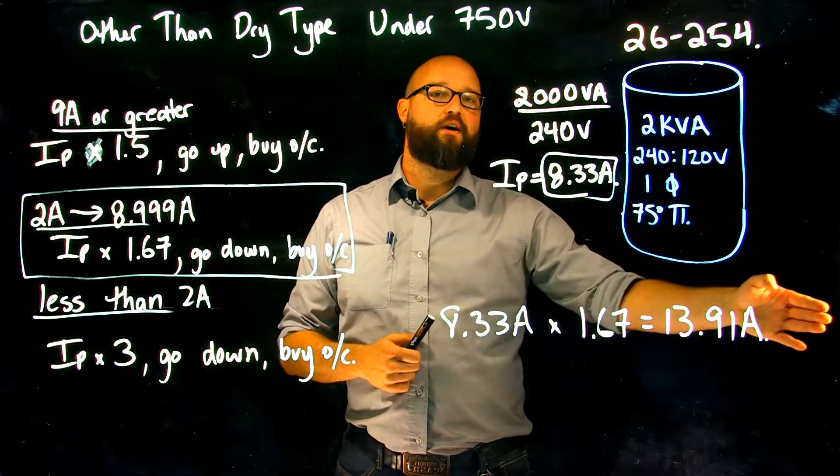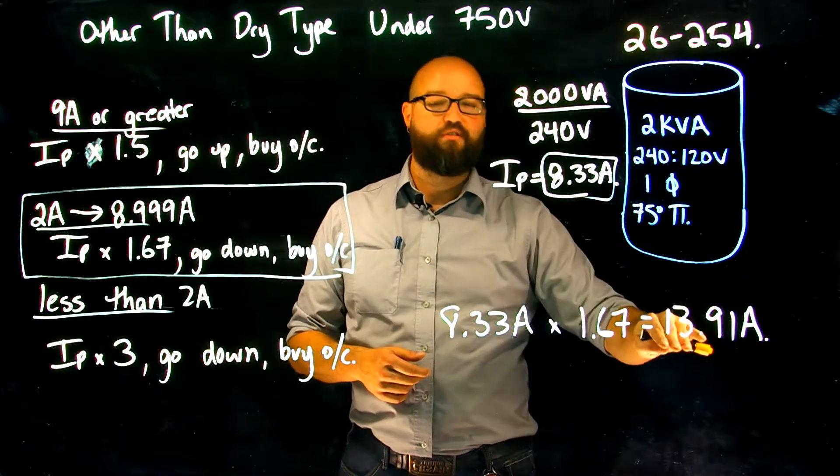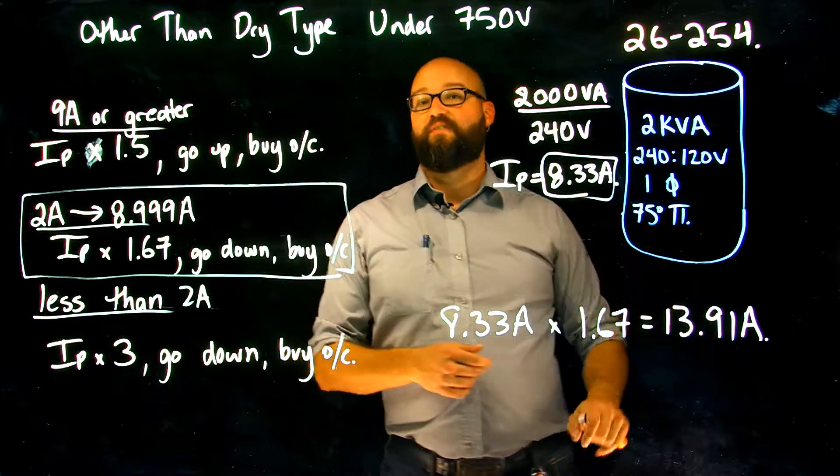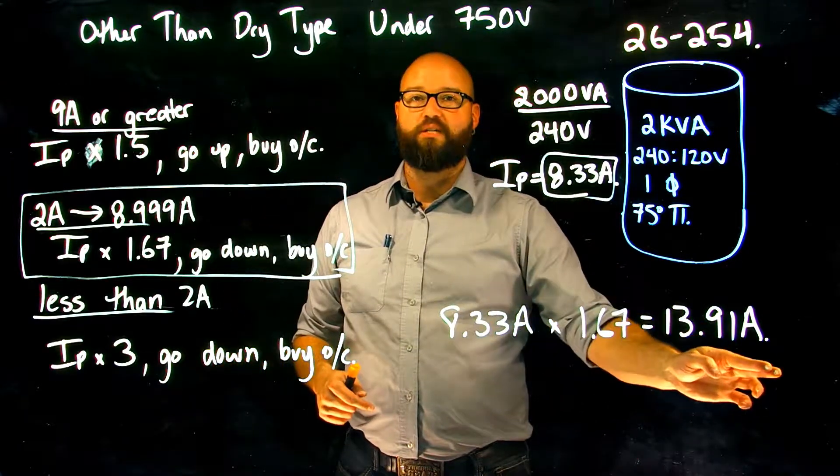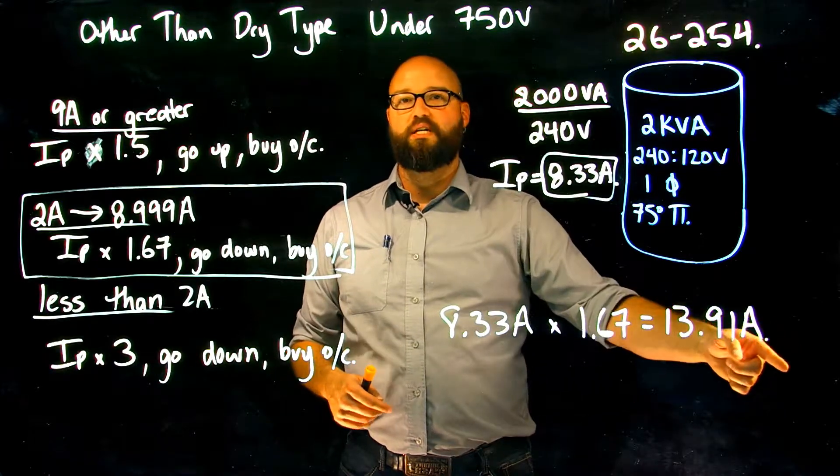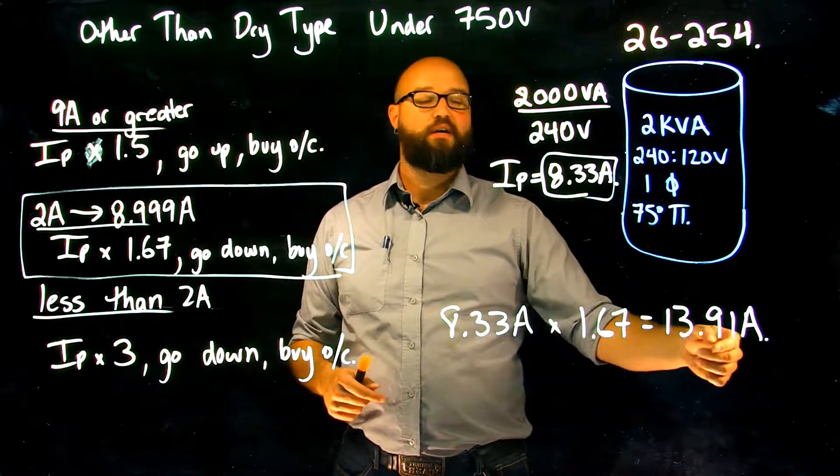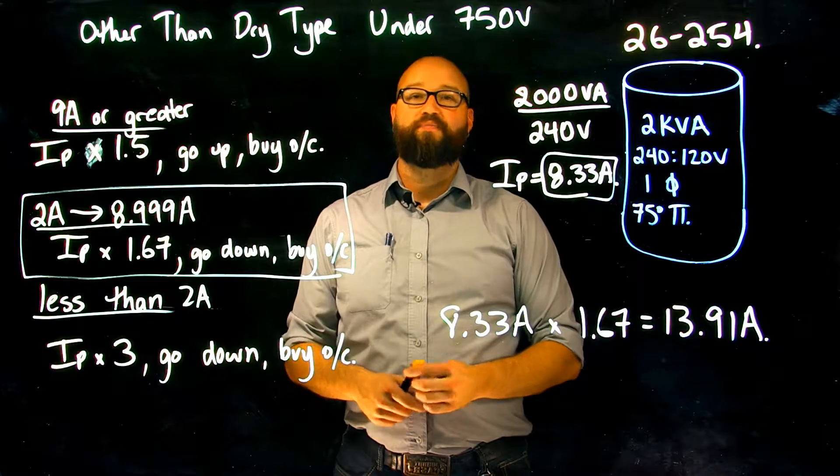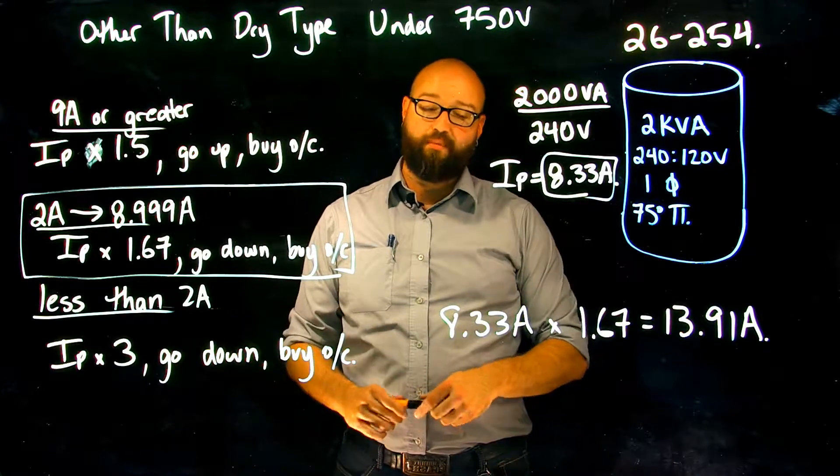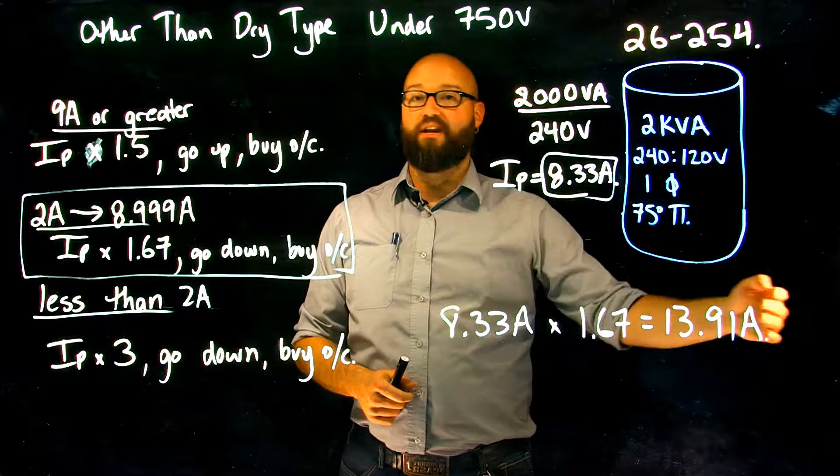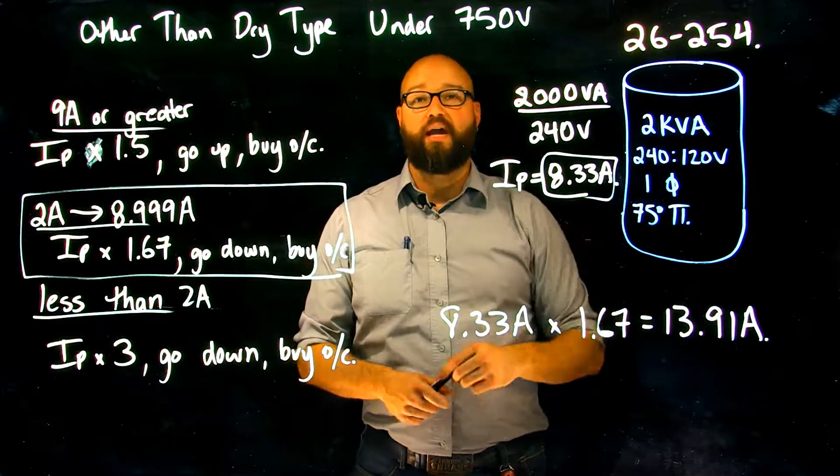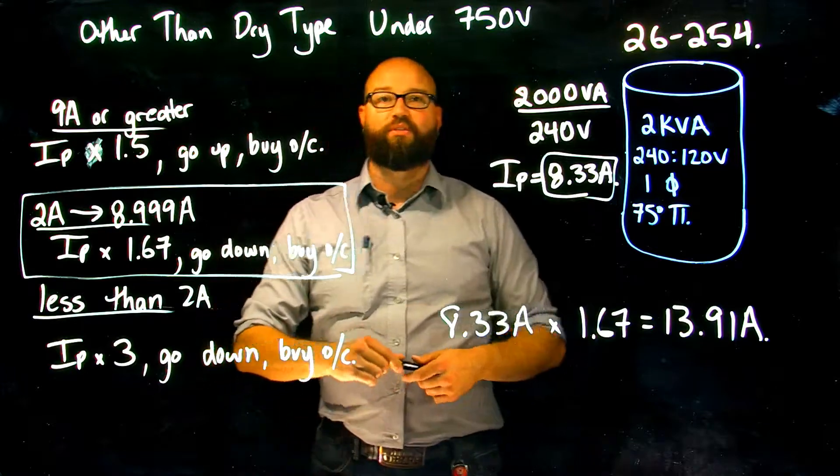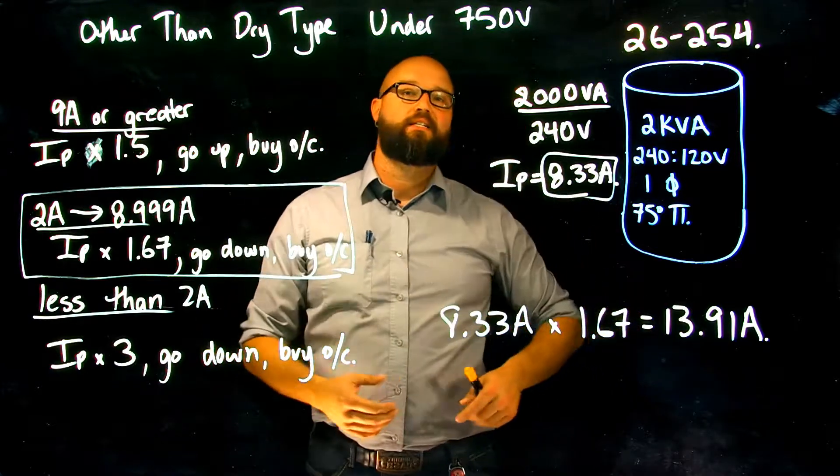If it was one amp increments, I would have a choice between 13 and 14. Again, if I went up to 14 I would exceed 167 percent, so I would go down to 13. If it was five amp increments, I would have a choice between 10 and 15 amps, and I would have to again go down to the 10 amp. And so on we could keep going with different increments, but the idea is whatever the increments are, pick the one that's underneath the 167 rating.